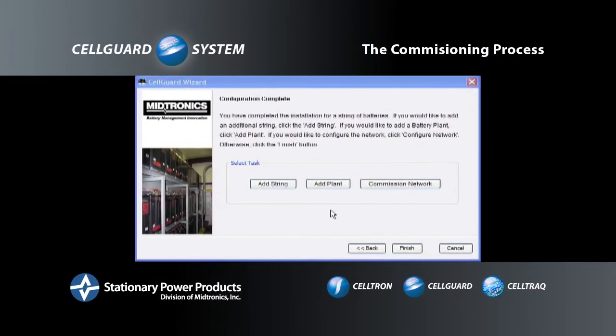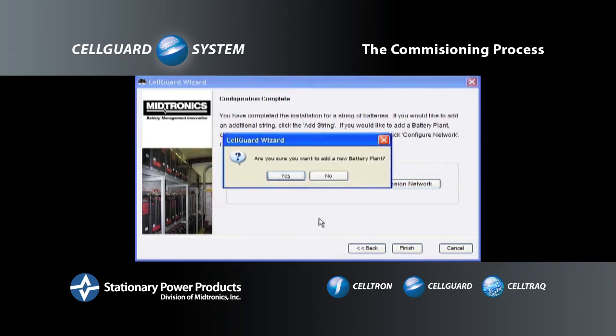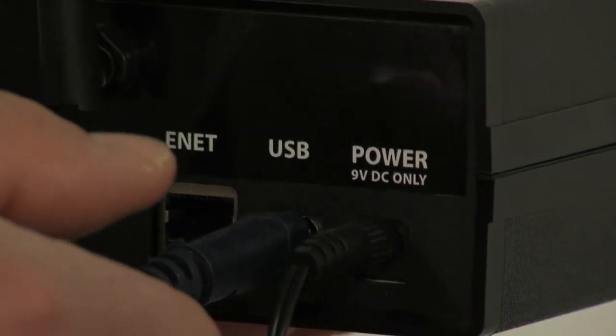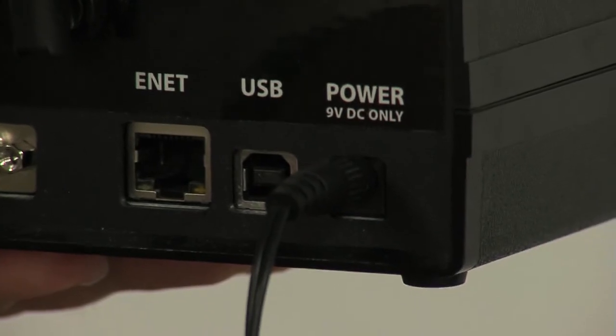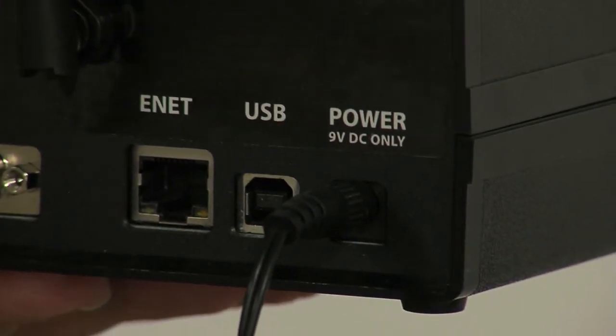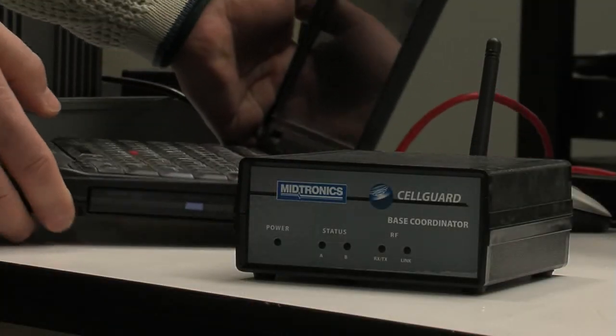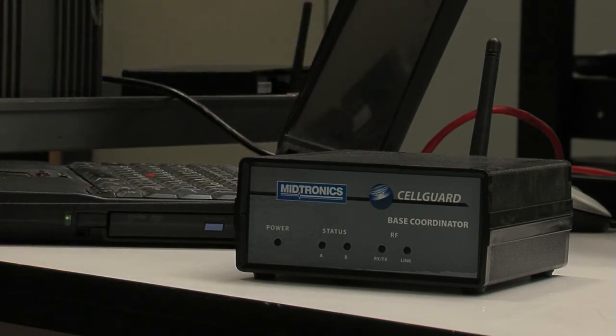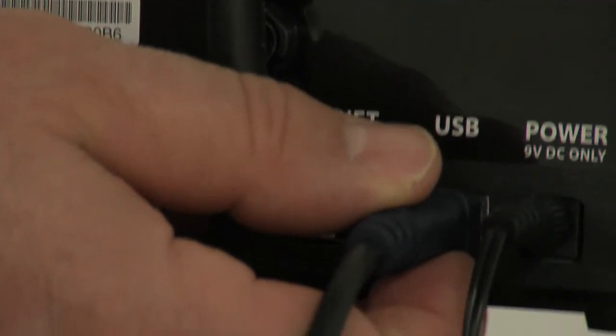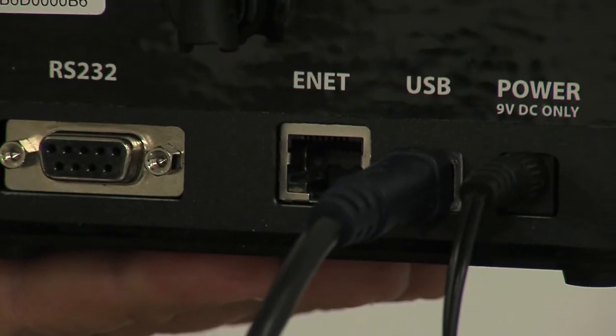To commission the hardware for a new battery plant, click Add Plant. A message will pop up asking, "Are you sure you want to add a new battery plant?" Click Yes to proceed. Disconnect the USB or RS-232 cable from the first BCU. Without closing the wizard, move your PC to the BCU for the new power plant. Connect the USB or RS-232 cable from the PC to the BCU.